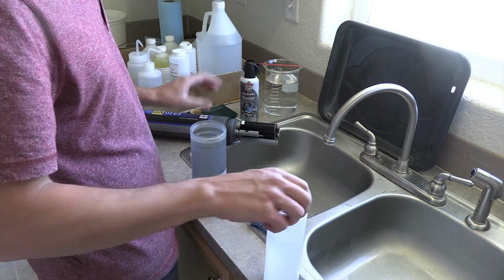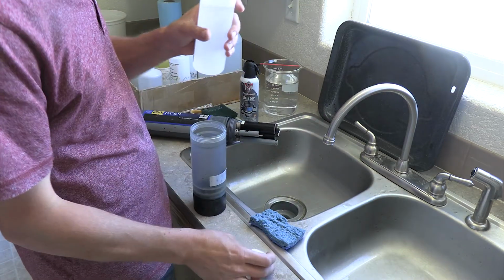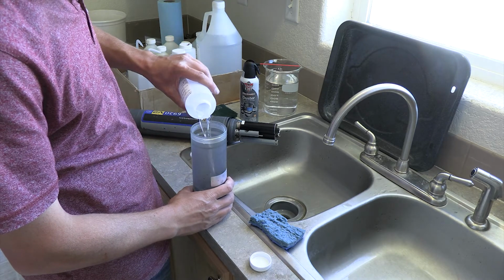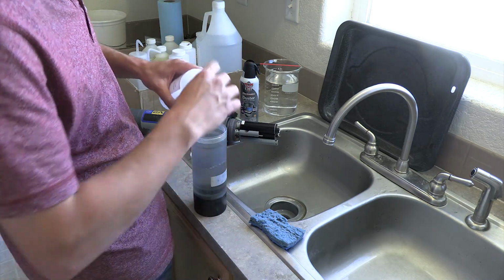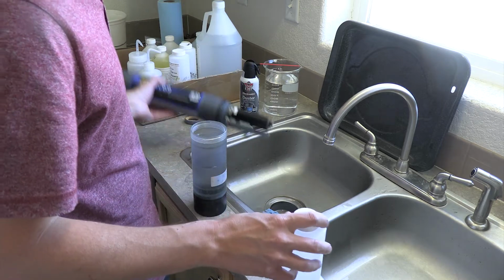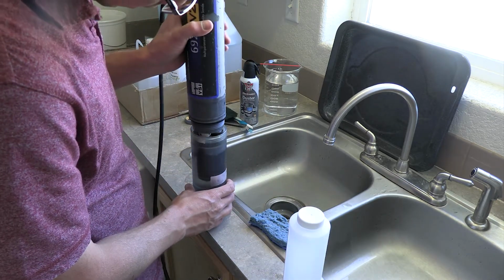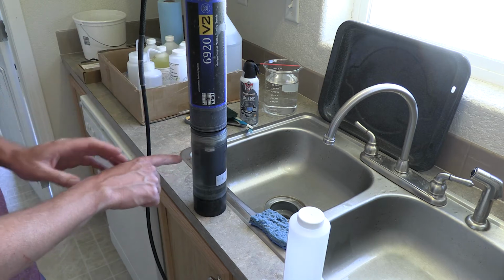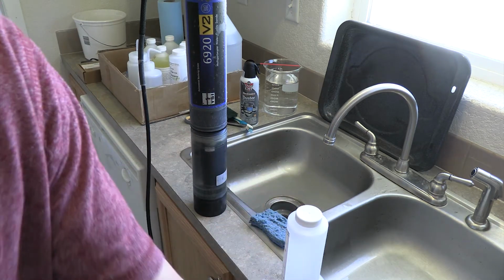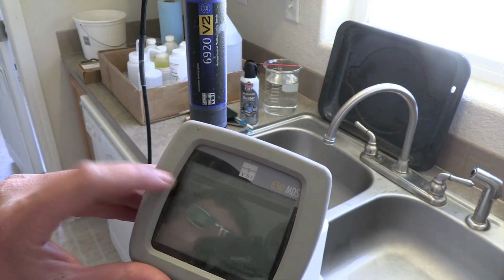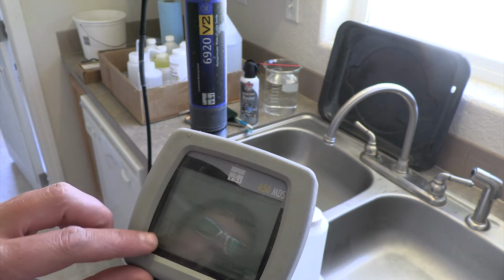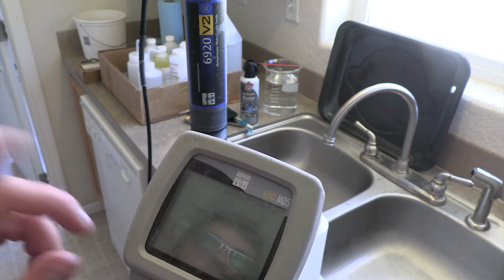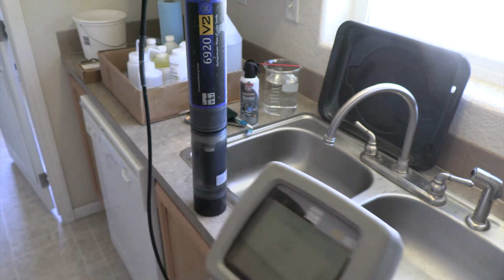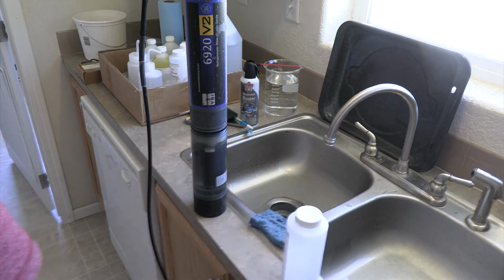Let's go ahead and fill this guy. Remember, this has to go really high because this is the main, it's the shortest probe. Make sure it's all the way over that little hole, and then let's go back over to our meter and press enter on specific conductivity. And then it's actually 1 because it's under millisiemens, not microsiemens. So press 1, let it run and just let it stabilize.